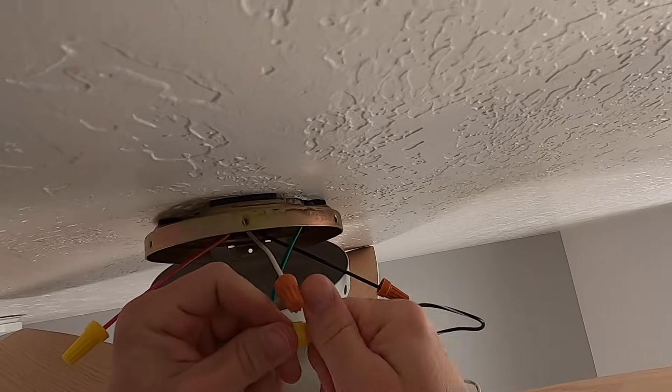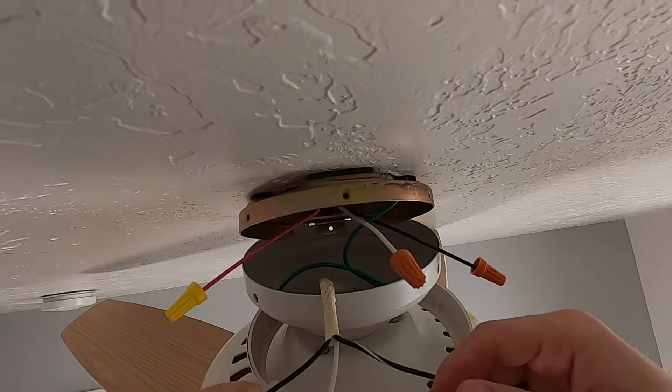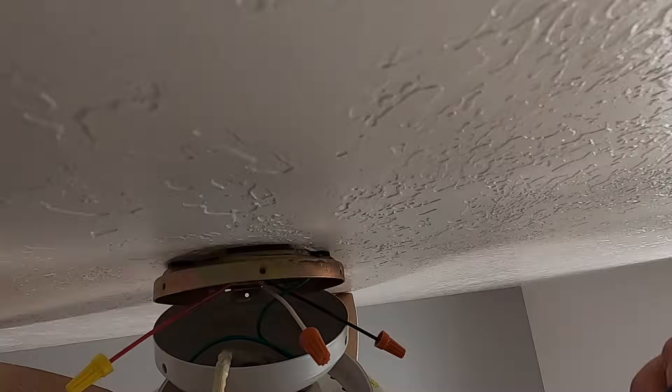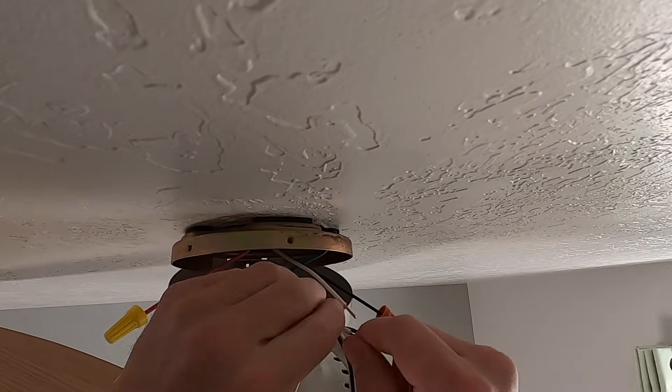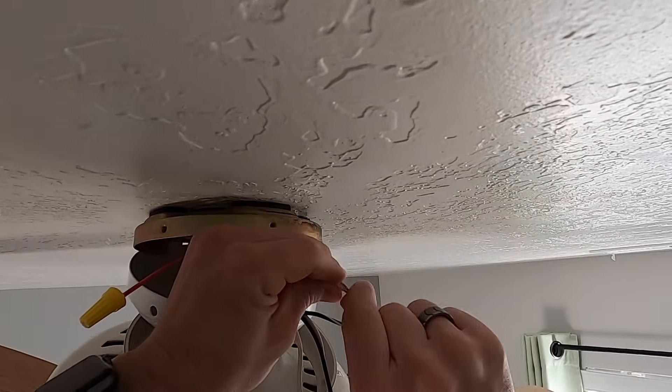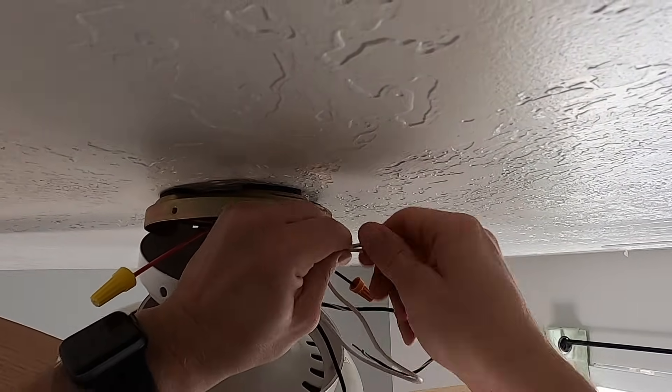Now, besides the ground, you should have three other wires coming out of your fan unit. It should be a black wire, a white wire, and a unique wire. This unique wire might be blue. In this case, it's black and white striped. Now, the second easiest besides the ground is the white. The white, you just connect to the white. This is your neutral wire.